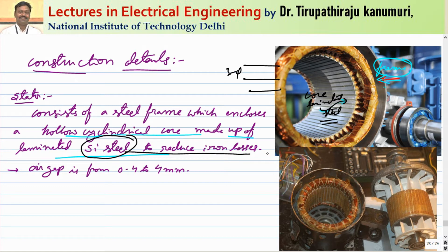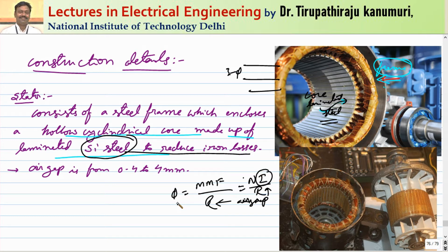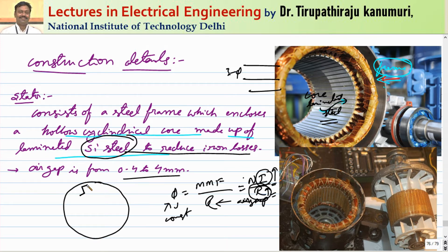The air gap between the stator and rotor should be as minimum as possible. Since flux equals MMF divided by reluctance, a larger air gap increases reluctance, which increases the magnetizing current required. That is why the air gap is maintained between 0.4 to 4 mm. The stator core has slots on its periphery, and in these slots the three-phase distributed winding is placed to produce the rotating magnetic field.